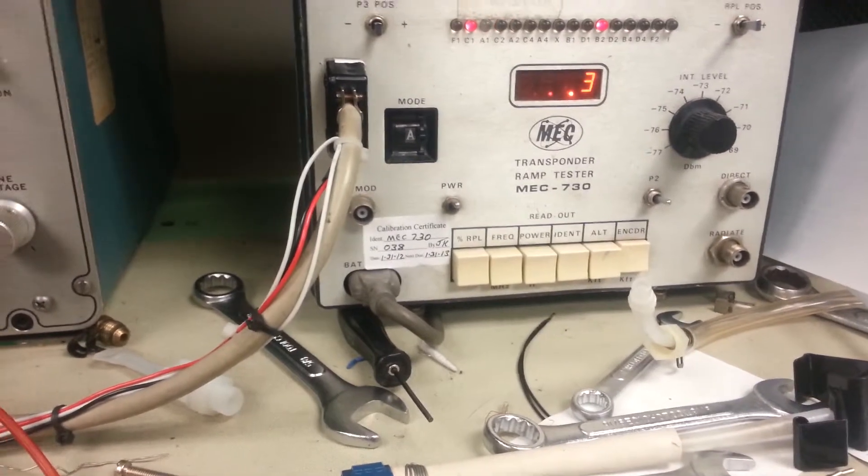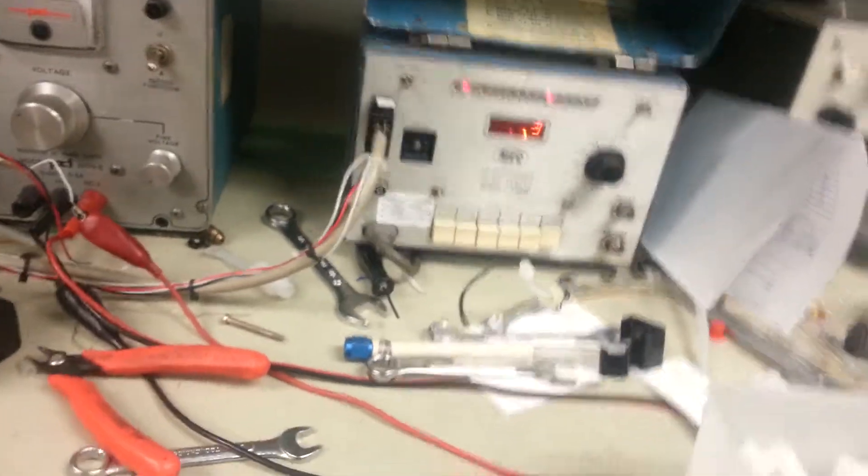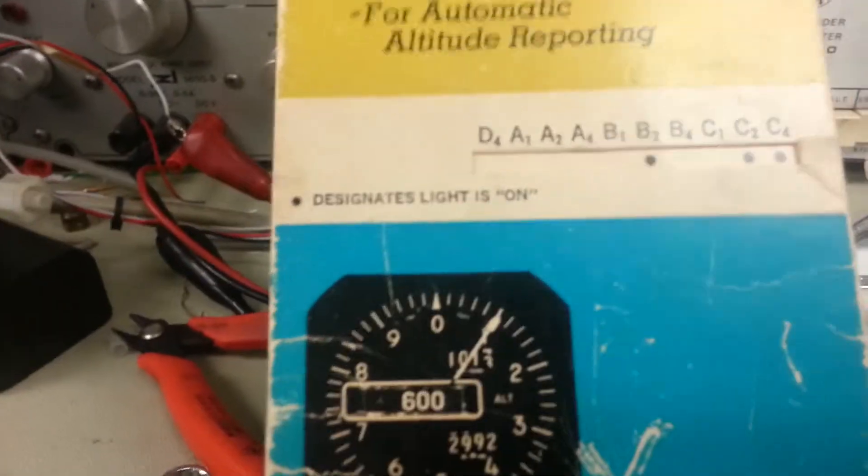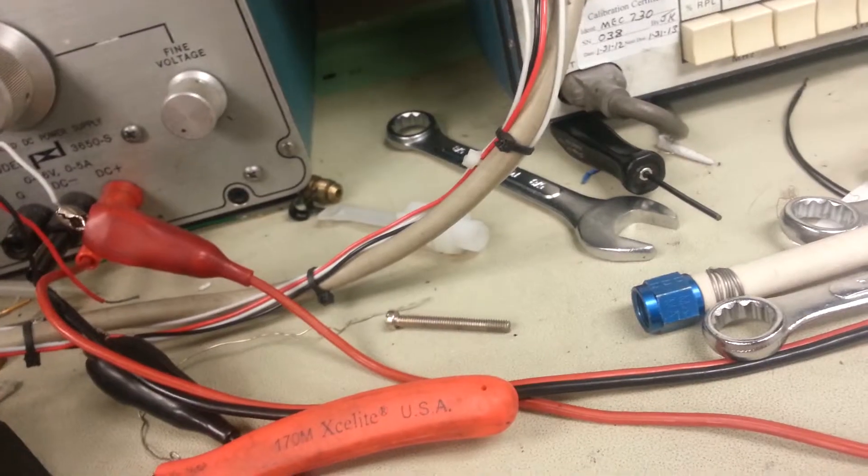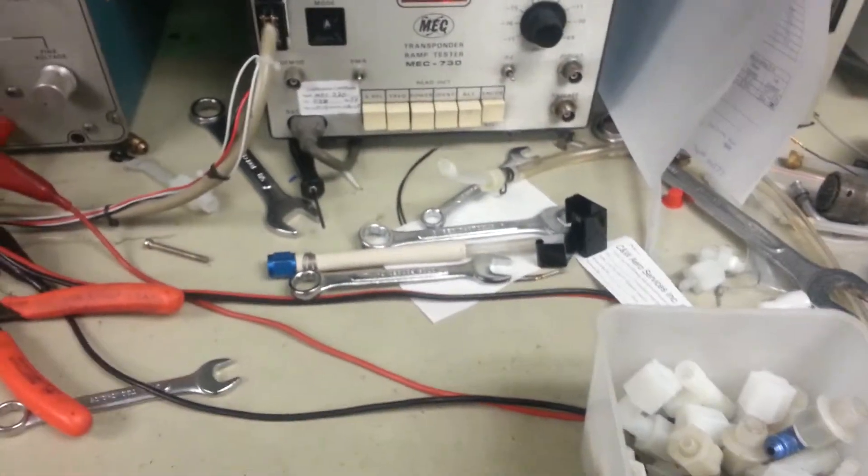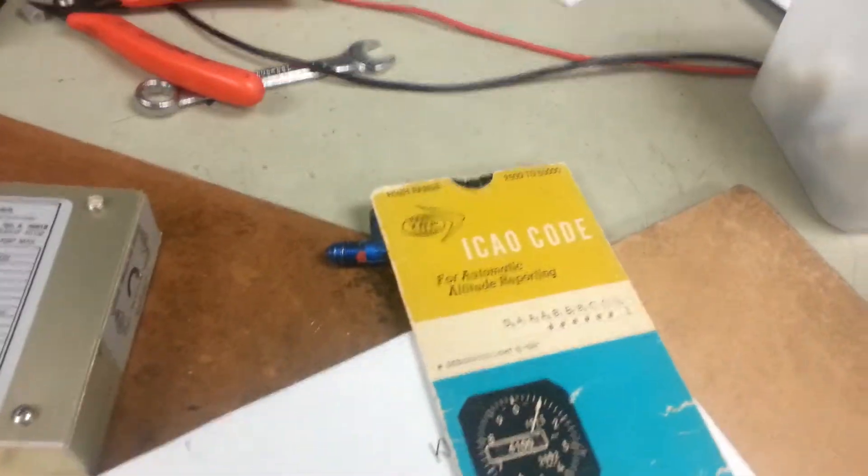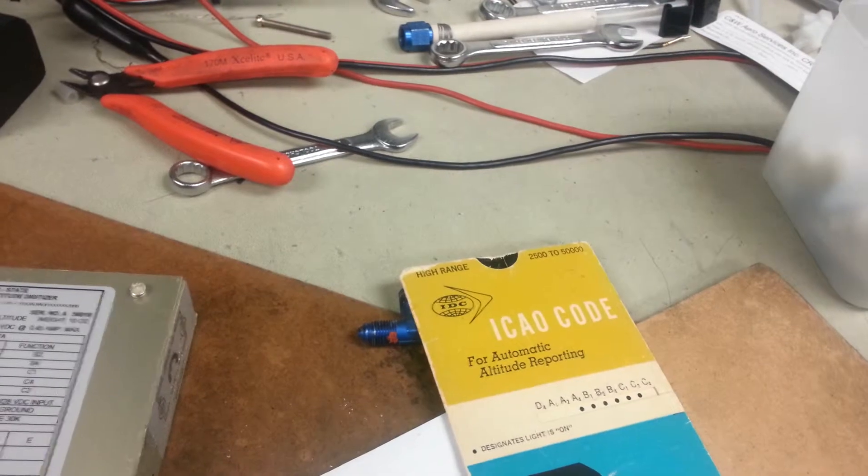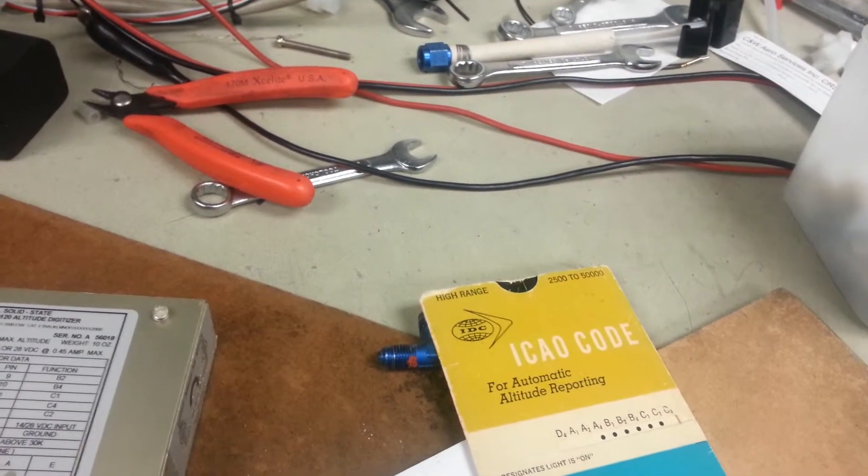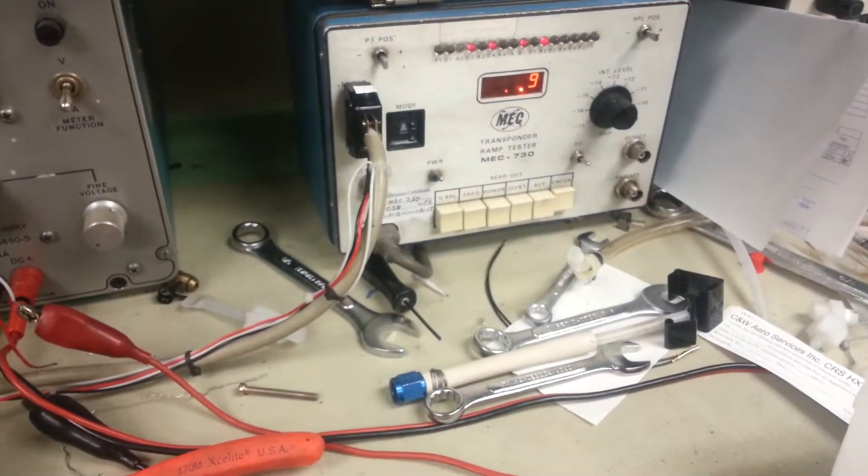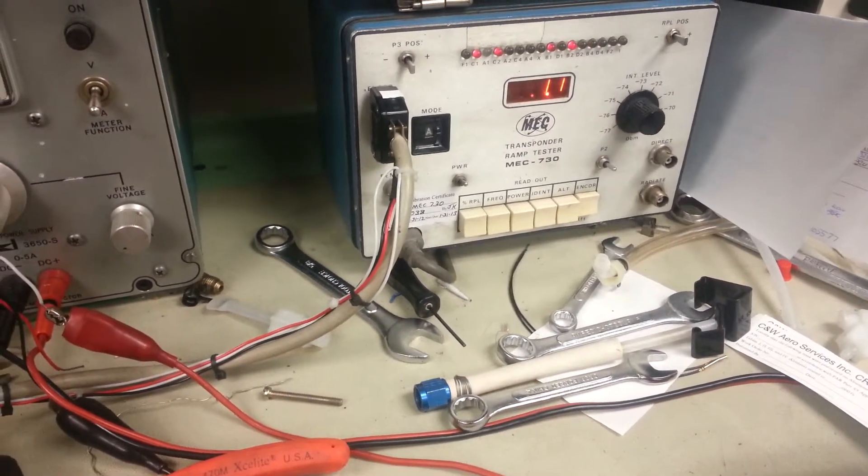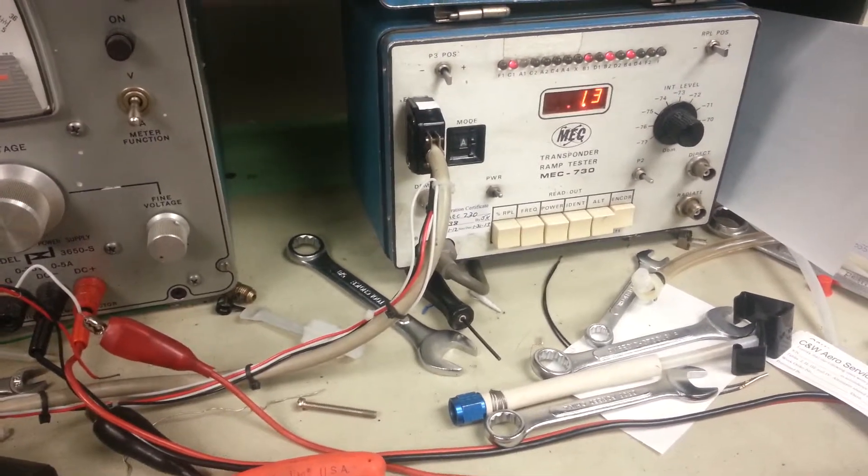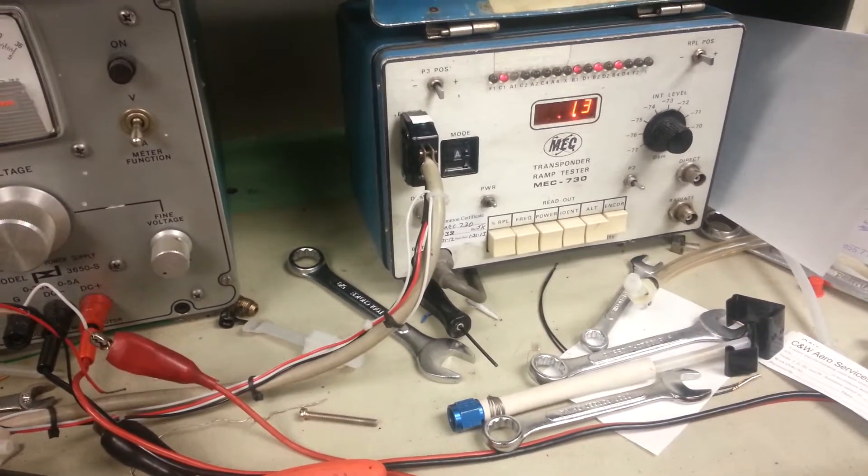Let's just say I'm going to put this on, let's go to a known altitude, let's go to 4,100 feet. I'm almost there. So if I bleed down, it's 48, they're coming down here, 44, 43, 42. And this encoder was pretty accurate before.